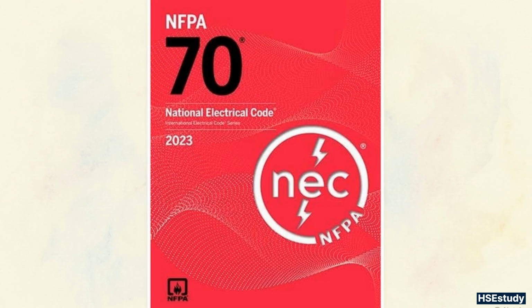Depending on the system's incident energy, the arc flash boundary can extend even further than the shock approach boundaries, creating a much wider radius where a worker could receive second-degree burns. The qualified person designation is a measurable physical threshold. It is an access control system designed to keep untrained bodies out of the blast radius.